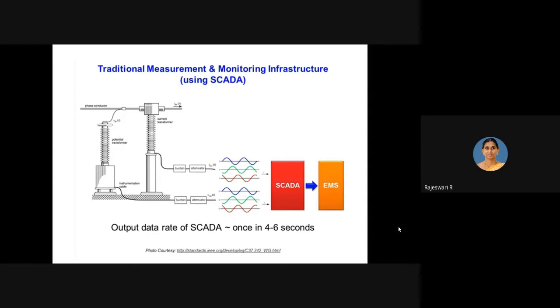The values are all declared in RMS, root mean square values being conveyed to the EMS. This is one of the main problems, because once in 4 to 6 seconds - our frequency of operation is 50 Hertz, so cycle time is 20 milliseconds. In 1 second, 50 cycles are being completed, so even in 1 second, many things could happen to our network.